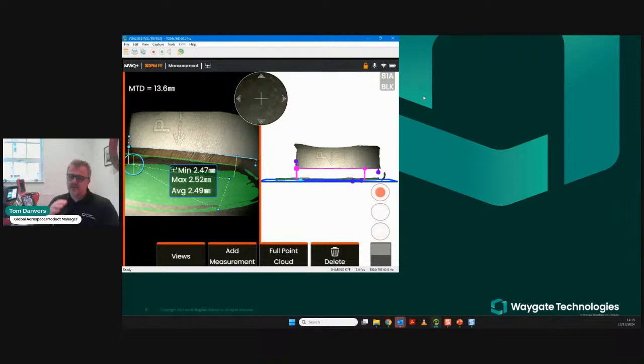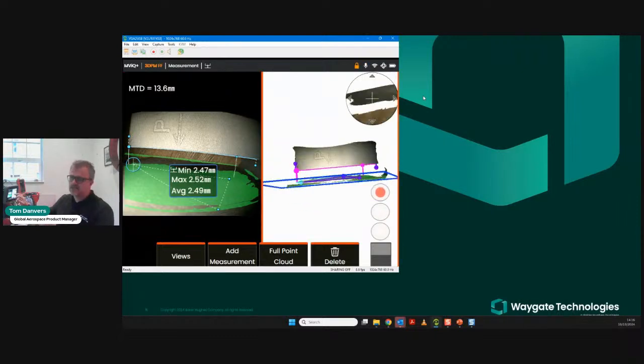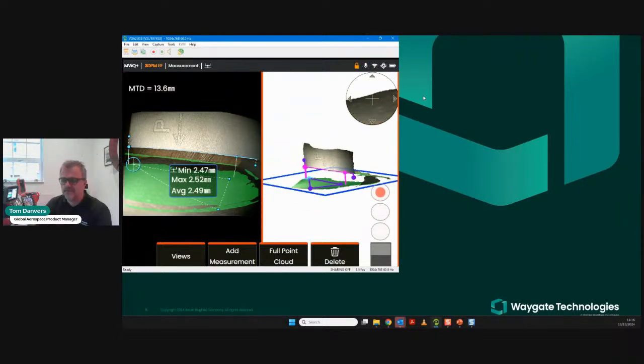But there's an example where I would have normally had to interact with the device 3 times. I'd have had to set 3D PM capture, then press the measurement button, and then press the blade tip clearance measurement tile. Instead of doing any of those things, I just said what I said, and I'm now in that state where, because I picked an automatic measurement type, it's actually done the measurement automatically for me. So you can see the point cloud on the right-hand side and the 2D image on the left.